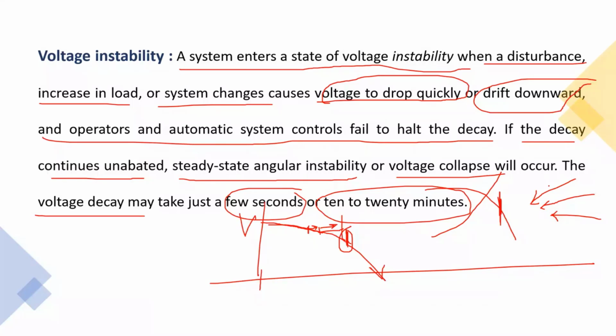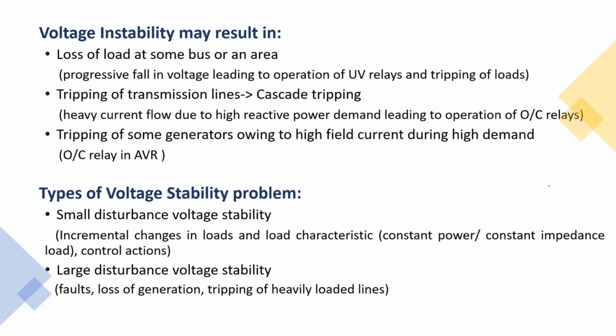So at that point of time, if you try to further reduce the voltages, there will be an immediate collapse in the system. All generators will be going out of step. They will not be able to sustain the reactive power into the system. This kind of thing has already happened in the past in India. There have been cases of voltage instability in the Punjab system. So that's why its ATC and TTC were calculated separately.